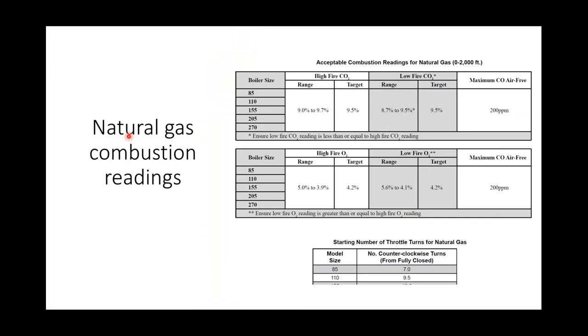For natural gas at sea level, these are going to be your ratings where you're looking for your high fire and low fire and your parts per million. Your approximate starting for your natural gas. All of this can be found in the I&O manual, which hopefully should still be with the unit. If not, it is available on our website, velocityboilerworks.com, and we'll have all these manuals available for you.